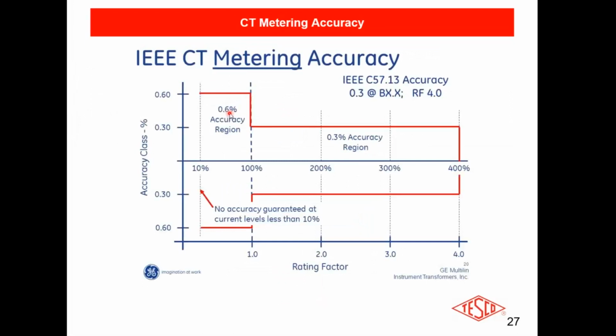This is your traditional instrument current transformer, not an extended range transformer. In this particular case, it's 0.3% accuracy class, so it makes it an instrument transformer, and it usually tells you up to what burden it's good at, a burden of 1, a burden of 0.5, and we'll talk a little bit more about that in a few coming slides.